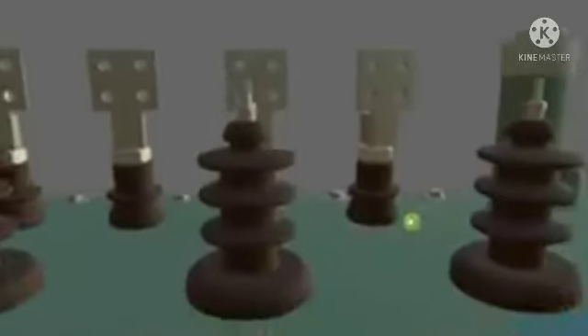If we go on the other side, we can see the high voltage bushings, and that would be these 3 here. 1, 2, 3. The giveaway for those is simply that the voltage has been increased, therefore the current has been reduced. So we can see the current carrying pieces of the bushing. That's this metal piece here, and this one over here. Those pieces are going to be a lot thinner because the current they carry is going to be a lot less. However, the voltage is going to be higher, and that is why they have more insulation than the low voltage bushings. So if you step up the voltage, you're going to need more insulation, and if you step up the current, then you're going to need a thicker conductor.